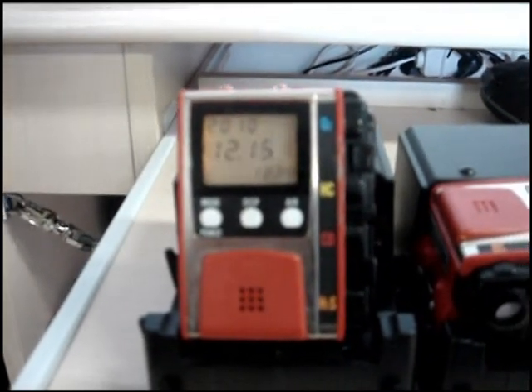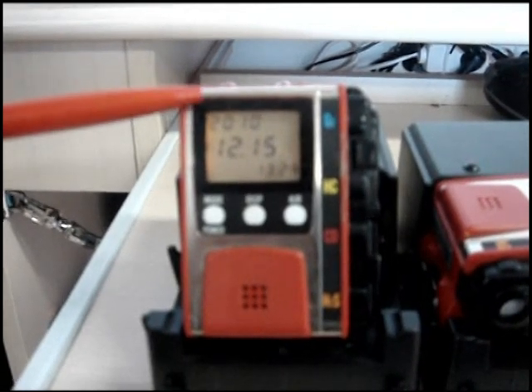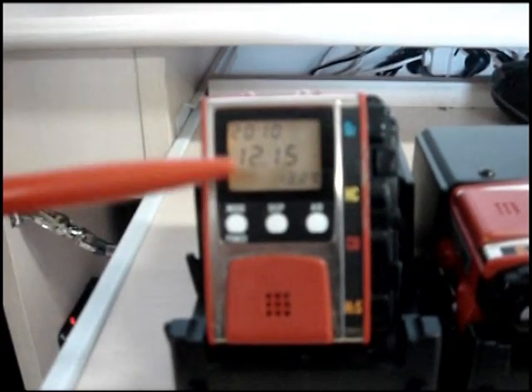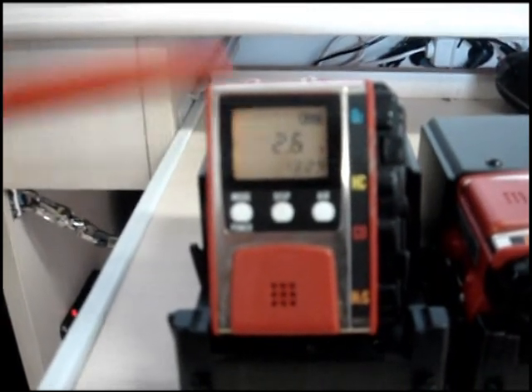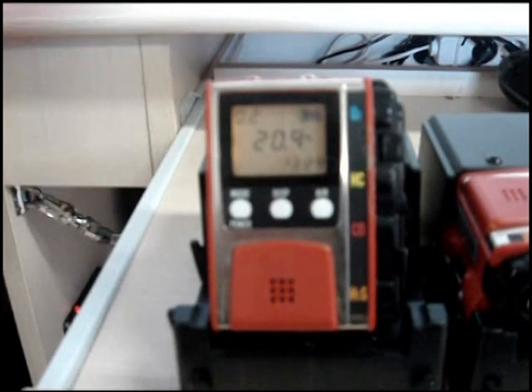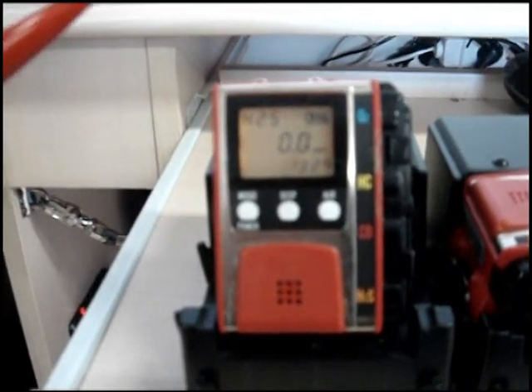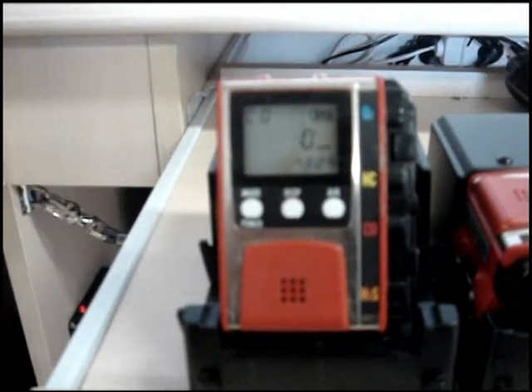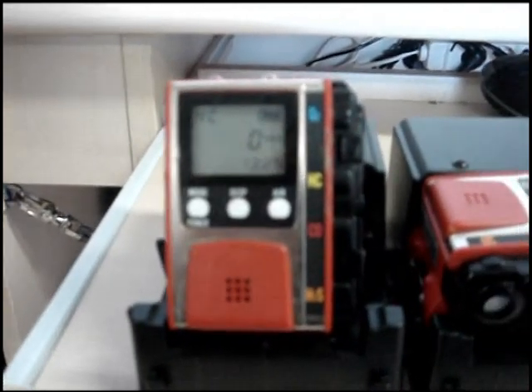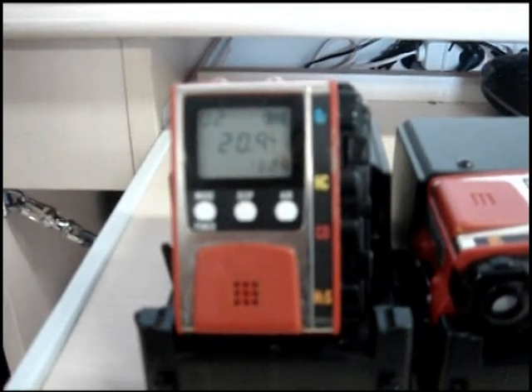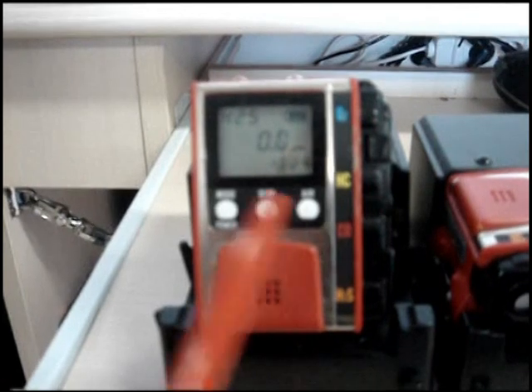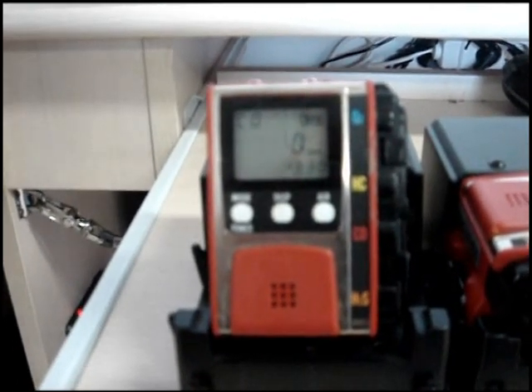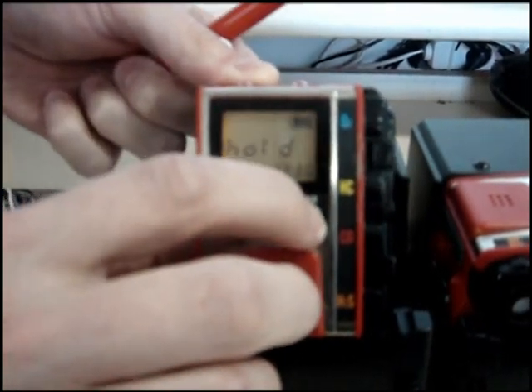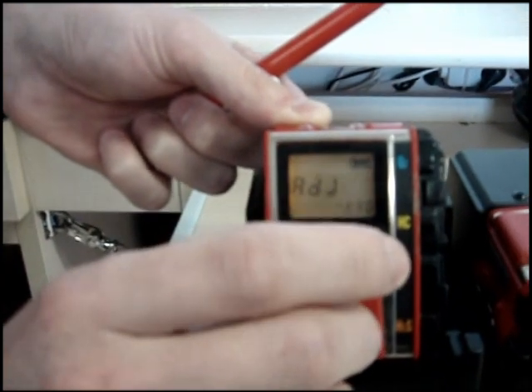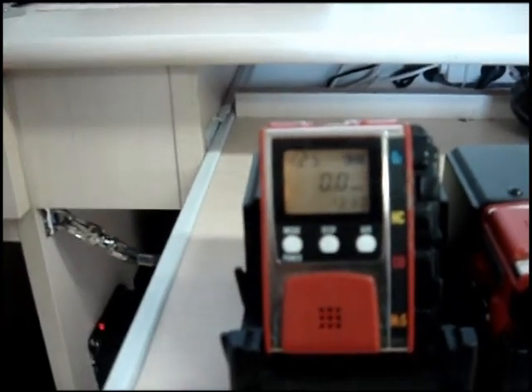Now the detector will show parameters like the date, year, and time. Then it shows the voltage of the battery, and later it will show you the components of gases it measures. Before each use, you have to make a zero calibration. This is made by pushing the air button and holding it as long as the hold message is shown. Now it's ready to be used.